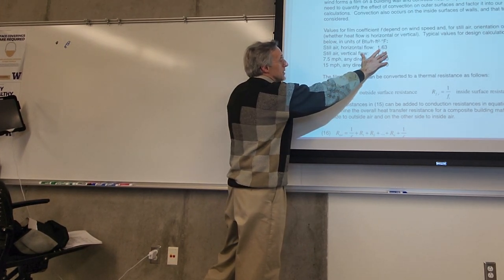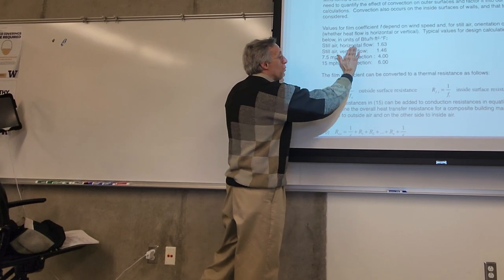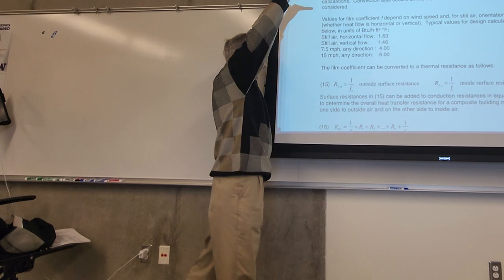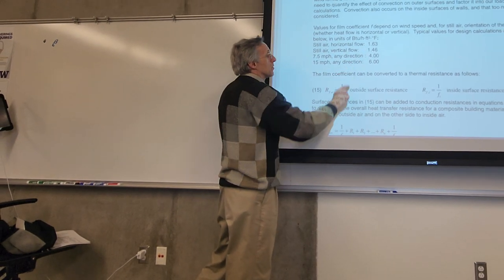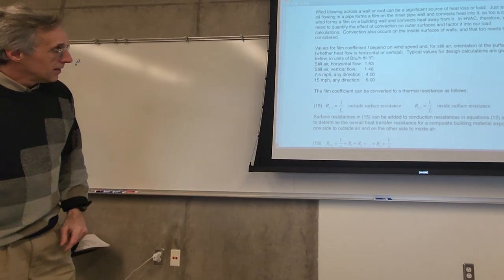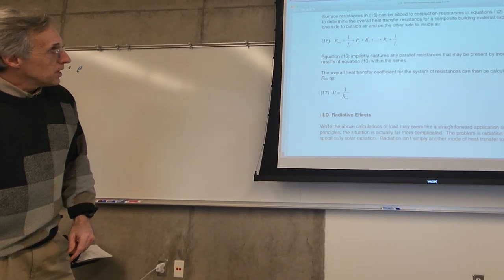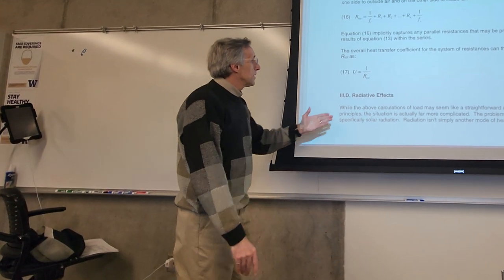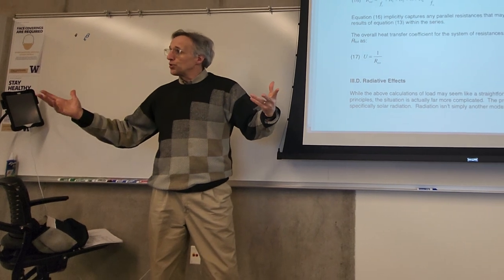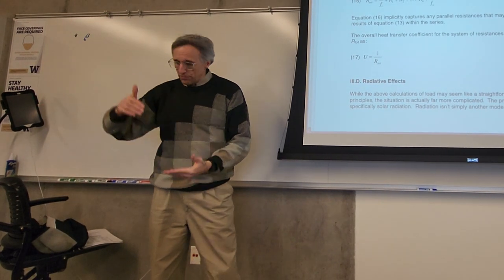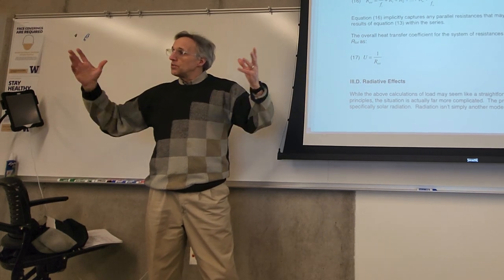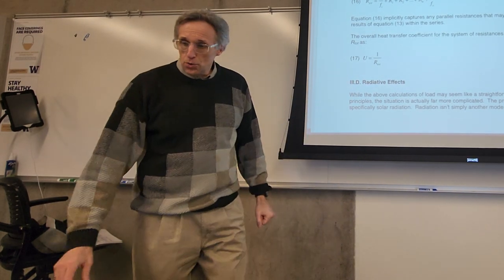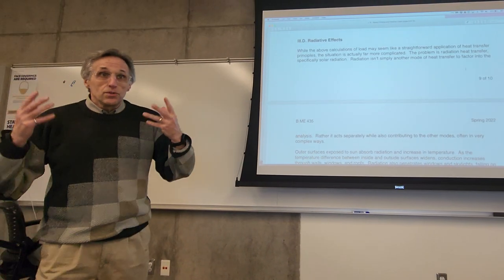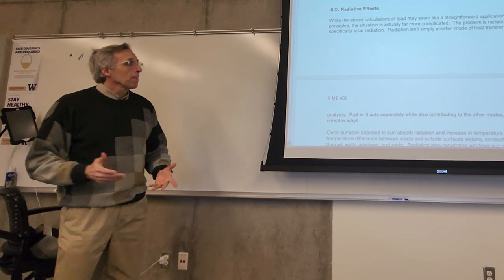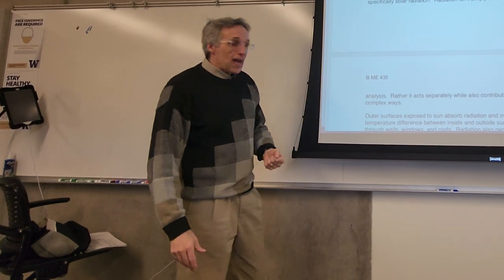So for a horizontal flow, this would be through a wall, 1.63, and then for the ceiling, 1.63. And we get all of these resistances, just add them all up and calculate an overall U value for the enclosure, for the entire enclosure: roof, ceiling, floor, walls, windows. You gather all the terms up, you calculate an overall U, and when you're calculating for heating in winter, you're done. And then in summer, we have to add in the radiation, the solar radiation component, but I'm going to hold off on that.